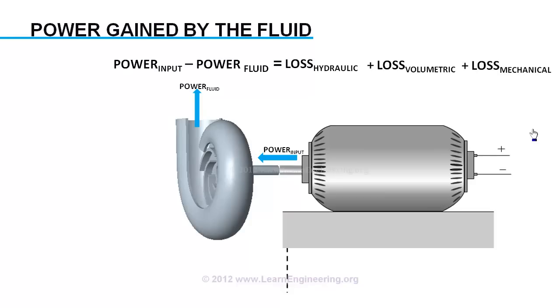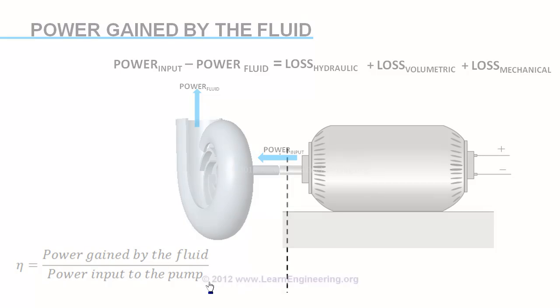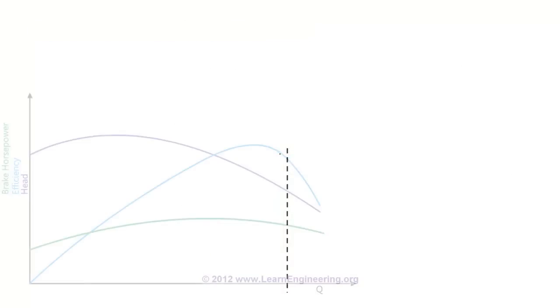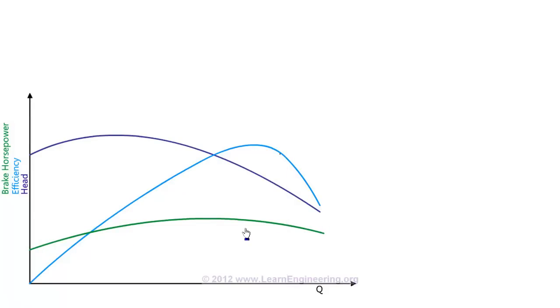So, efficiency of a pump can be defined as power gained by fluid divided by power supplied to the pump. For a typical centrifugal pump, efficiency will vary like this. Corresponding shaft power variation is as follows. You can note that there is an operating point in the pump where efficiency is maximum. It is known as the best efficiency point. It is marked on the head curve here.